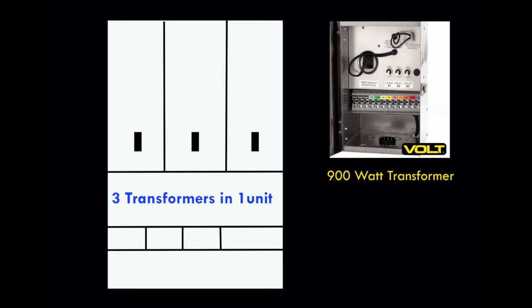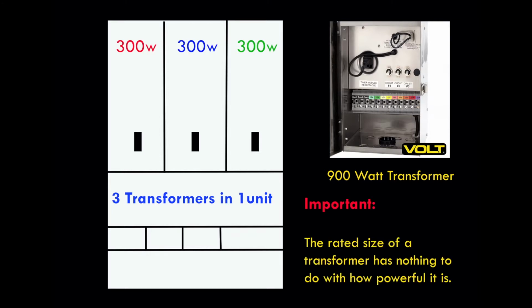To the right you see a picture of a 900 watt transformer. Now the easiest way you can tell that this is a 900 watt unit is simply by counting the number of circuit breaker switches it has inside, which in this case is 3. All of Volt's transformers, with the exception of the 75 watt unit, are 300 watt transformers. Now to clarify, our 900 watt transformer is simply nothing more than 3 individually breaker protected transformers stacked side by side in one case.